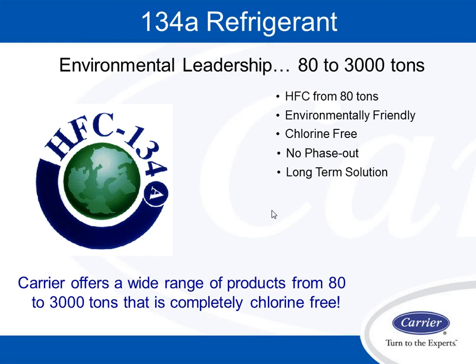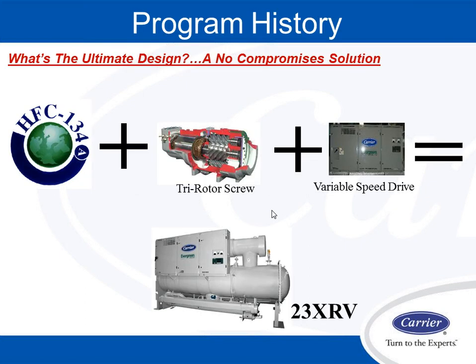I mentioned before, this is something that we feel, obviously the majority of every manufacturer uses 134A refrigerant. There's one manufacturer that is still sticking to their guns with 123, and that refrigerant, they can no longer sell chillers in this U.S. market after 2020. So that's less than 7 years away. We are talking about operating life before that chiller plant has a refrigerant that is basically extinct, in that there'll still be refrigerant out there, but the only place that it's allowed, 123 is produced, is for centrifugals for that manufacturer. So we feel with no phase-out date with 134A, 134A was obviously the right choice for refrigerant.